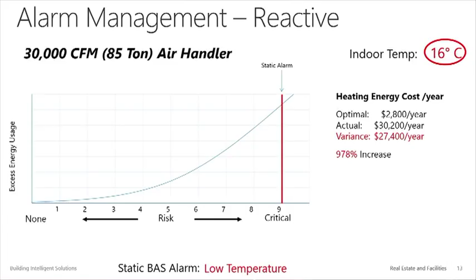Things start getting a little worse, and maybe nobody in the building knows it. This is the value of analytics. If it's 21 degrees in the building, nobody's calling maintenance saying there's a problem. It's not an alarm condition, so the building system isn't saying there's a problem, but we're wasting energy and we don't know it.